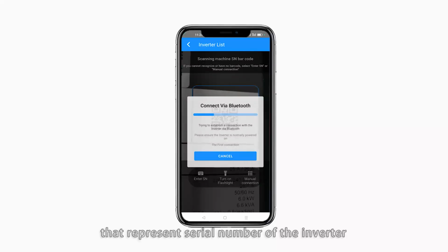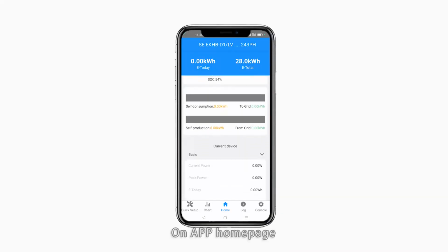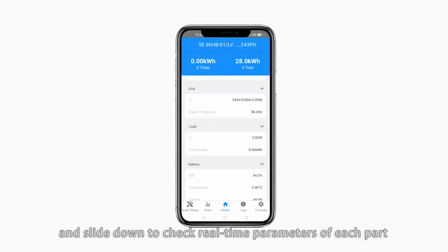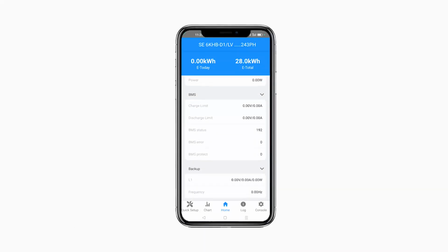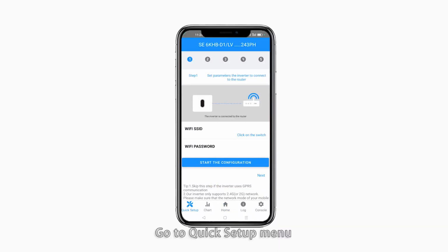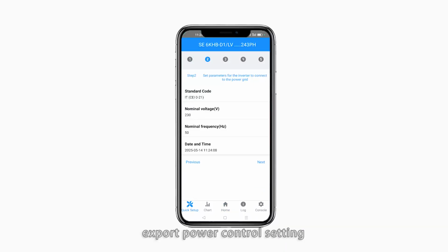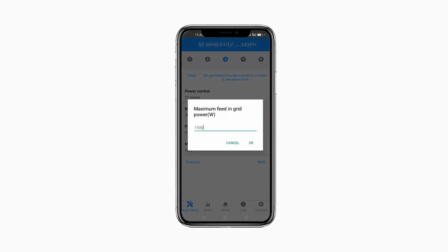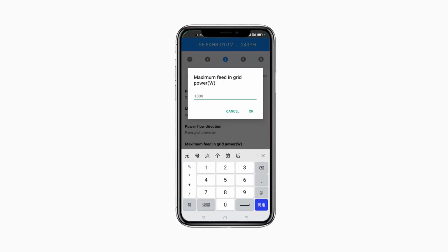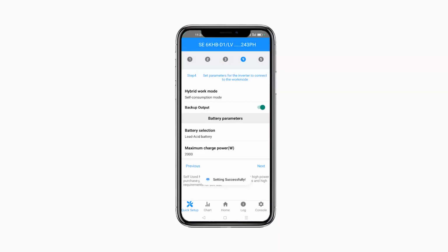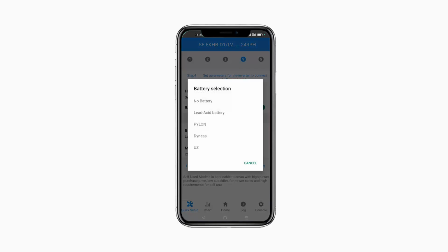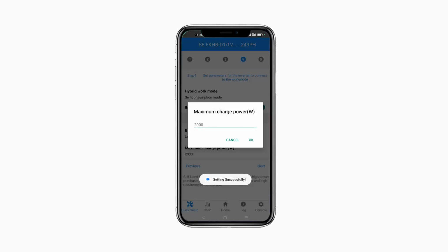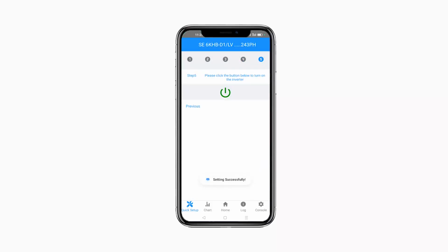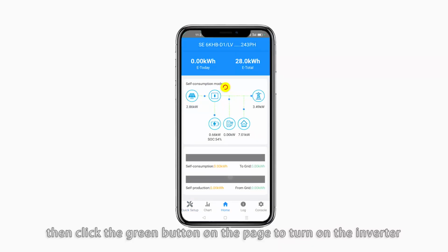Scan the barcode that represents serial number of the inverter. On App Homepage, you could overview system status and slide down to check real-time parameters of each part. Go to Quick Setup menu, confirm regulation setting, export power control setting, and working mode setting. Then click the green button on the page to turn on the inverter.